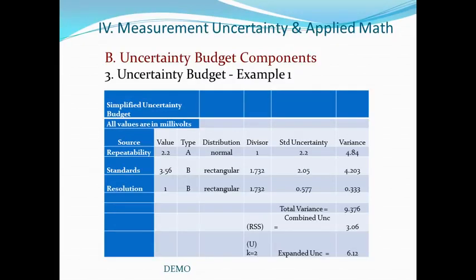Since we did not do our own statistics on this number, we must apply some type of distribution other than the normal. So we have a type B distribution in this case. Since we are taking off a value of the plus and minus spec limits, this would be a rectangular distribution, and we would have a divisor of 1.732, which is equivalent to the square root of 3, which is the divisor that we use to normalize a rectangular distribution into a normal value. The next column is standard uncertainty, and so we divide 3.56 by the divisor 1.732. Here we come up with a standard uncertainty of 2.05 millivolts, or squaring that gives us the variance of 4.203.